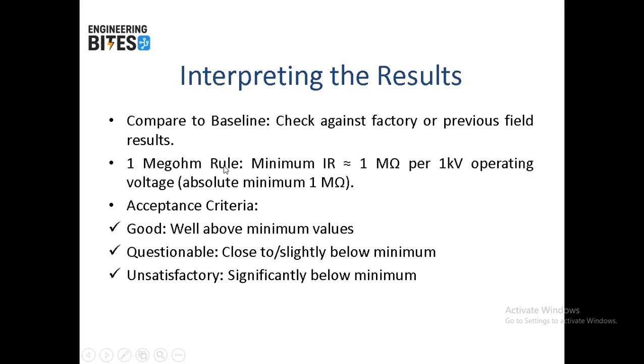We will compare the baseline. We must compare to baseline values, like we check against factory or previous field results. We apply the 1 megohm rule, which implies that the minimum insulation resistance must be equal or close to 1 megohm per 1 kilovolt operating voltage, and the absolute minimum is 1 megohm. The acceptance criteria: when it's well above minimum values, it's considered good. When it's close or slightly below minimum, it's questionable. When it's significantly below minimum, it's unsatisfactory.